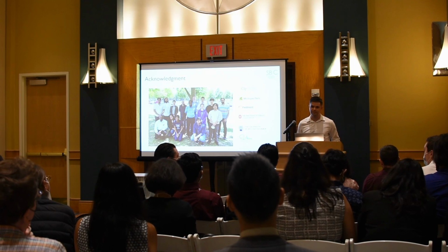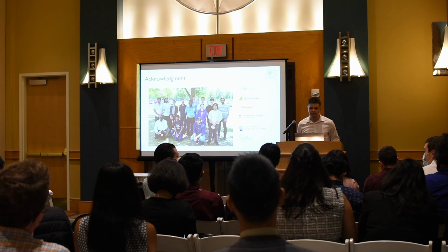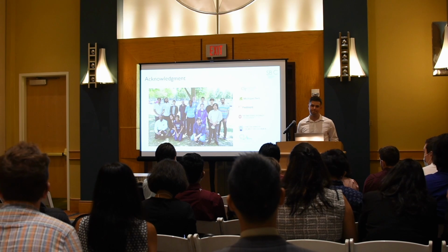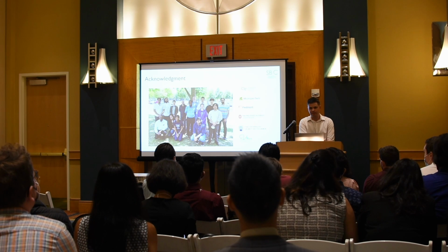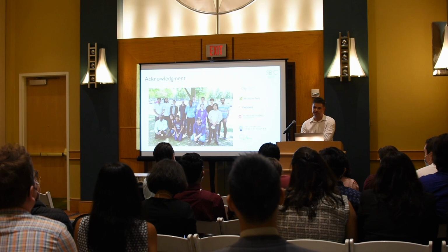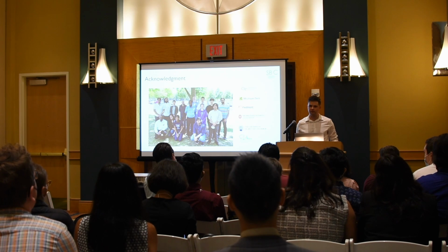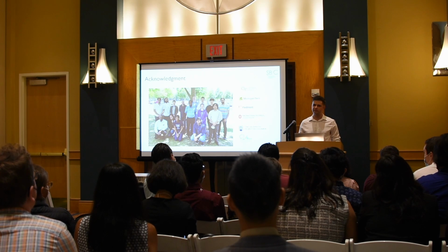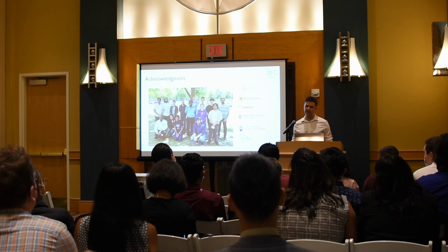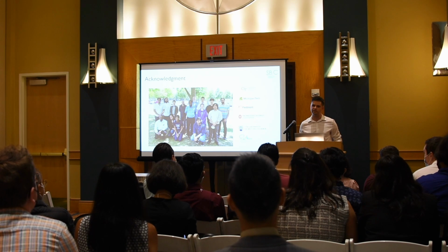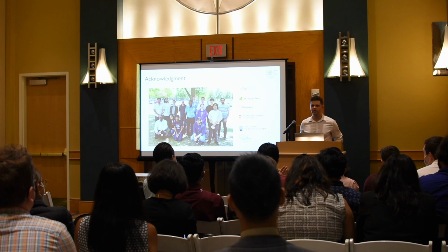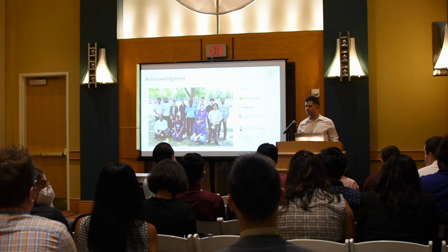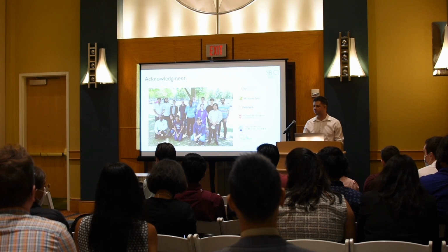Interesting talk, first of all. The question I have is for the valves that we have, is the thickness the same? No, some of them were bovine, some of them were porcine. So the porcine were thinner. So it might be one of the reasons that you have more fluctuations in the porcine valves. For example, Sapien is bovine, has less fluctuation. Might be one of the reasons. It's thicker. And is all the material coverage the same? No, almost, but I think bovine is more rigid, right? Yeah, the leaflet is thicker. Thicker and rigid.